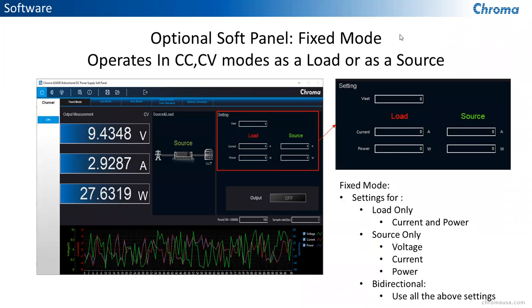And it gives you a great graphical display of the voltage, current, and power. It also gives you a display of what it's operating as, a source or a load. It'll even give you a graphical display of the direction of current flow through the device from the UUT, from the grid to the UUT through the source, or when it's acting as a load, it'll show it in the opposite direction. So you have voltage, current, power settings here. You can also do a graphical capture of the voltage, current and power, and you can do that at different data points, or the width of the capture, as well as the sample rate.